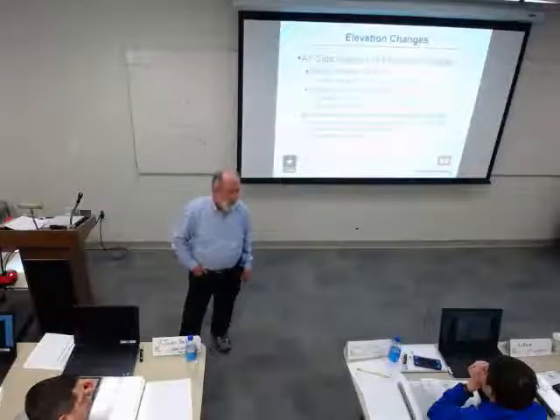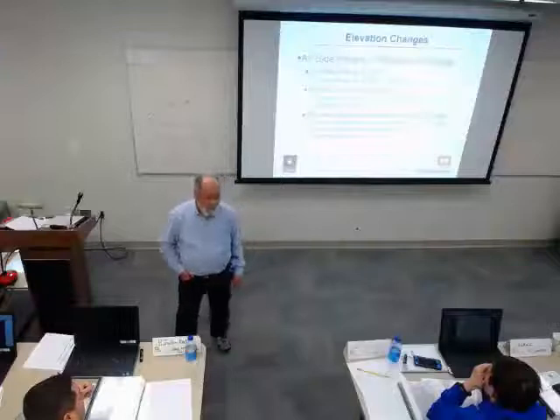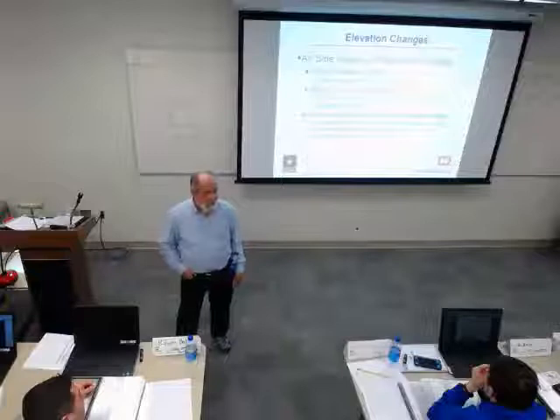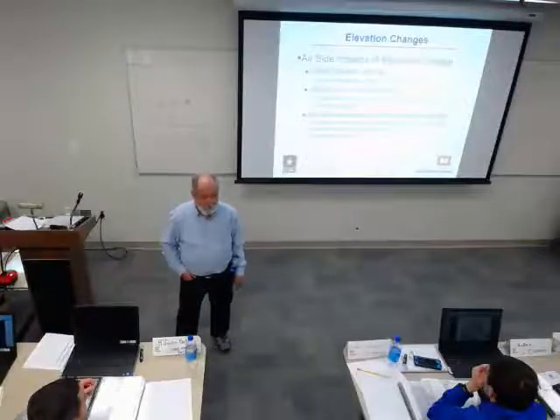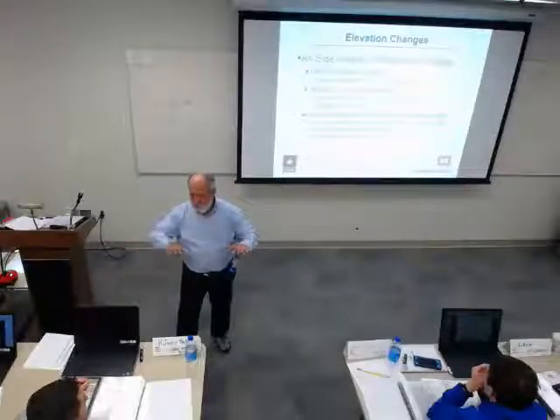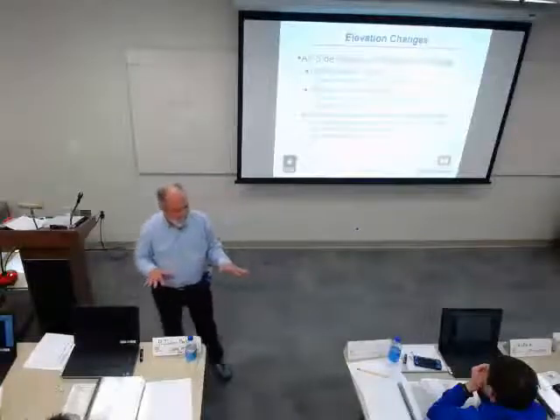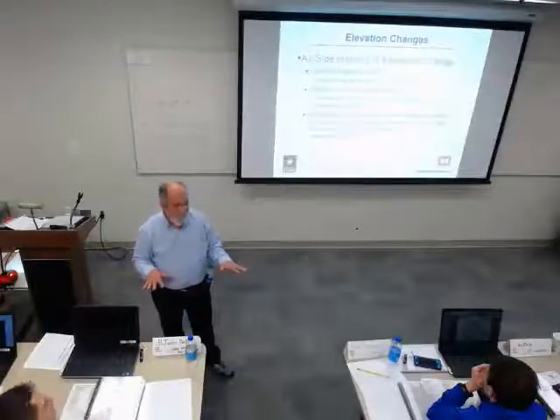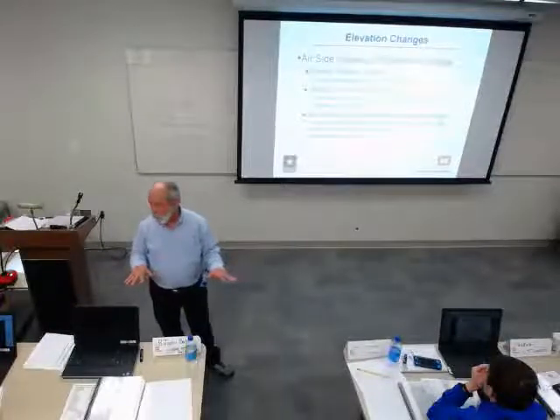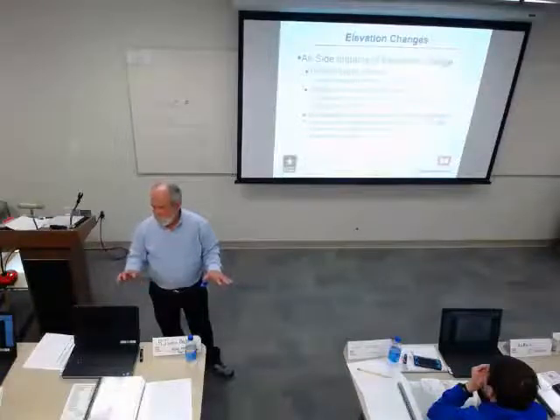Yeah, and from what I've found, I'm pretty happy if I can get between about 92% and 108%, then I think I'm pretty tight, and I have a high degree of confidence. When I see something like a 50% difference, I go, whoa, or 25%, whoa. There's kind of a judgment thing, and as you see these numbers very often and get familiar with them, you'll get a sense for what's a reasonable difference. And you go, whoa, this guy just blew it up. That is usually more obvious than a few points here or there. So if you see a big blow up, then you know that something is wrong. If it's within 8 to 10% of a difference, I wouldn't be too worried.